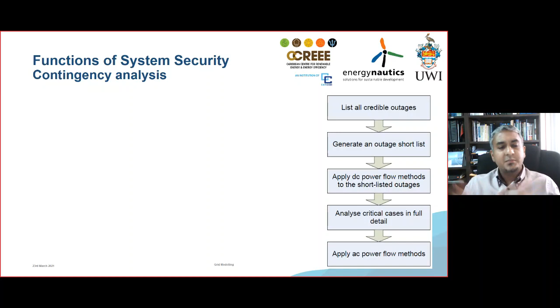The most appropriate model to use is the DC model. Why? Because it's very fast. It gives us the flexibility to perform multiple simulations and get an idea if a solution can work or cannot work. And if it can work, we go and do a full analysis, applying an AC power flow, the Newton-Raphson full power flow, so we can get a measure of the real, reactive, voltage angle and voltage magnitude across the entire network, not limited to any one particular assumption.